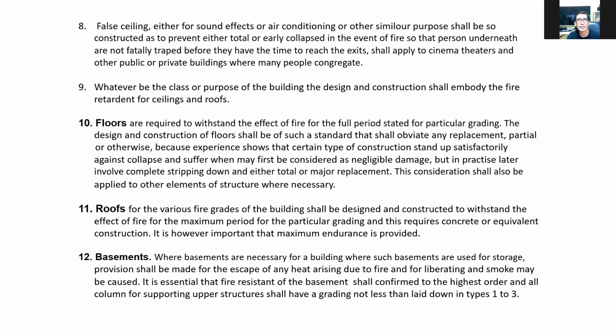So basements, where basements are necessary for a building and are used for storage, provision shall be made for the escape of any heat arising due to fire, and for the liberated smoke that may be caused. It is essential that the fire resistance of the basement shall conform to the highest order, and all columns supporting upper structures shall have a grading not less than that laid down in type 1, 2, 3.